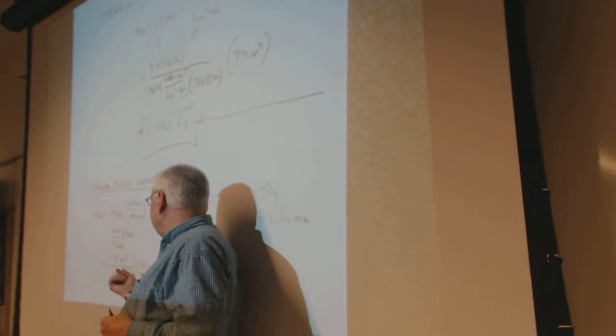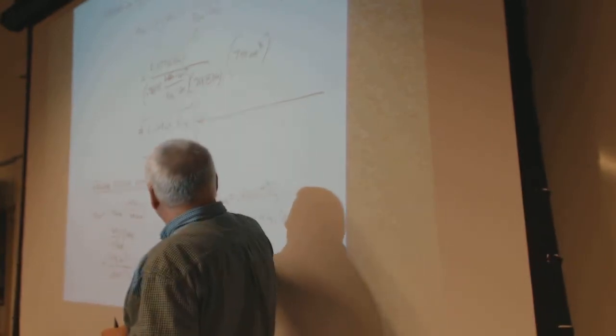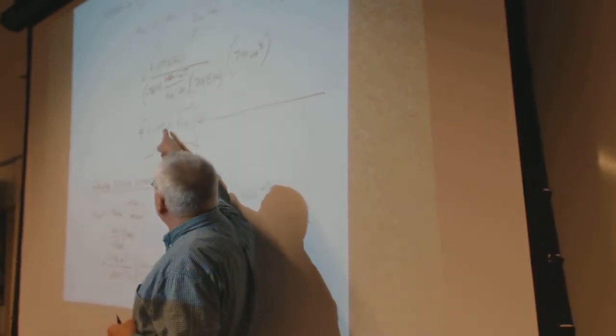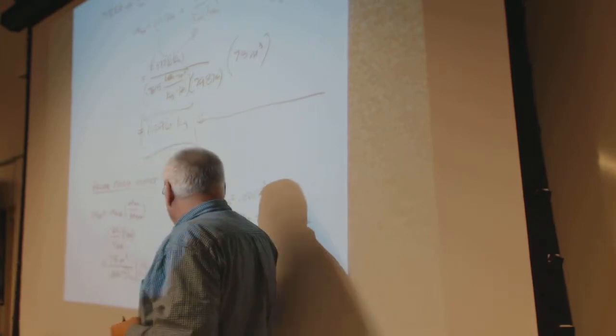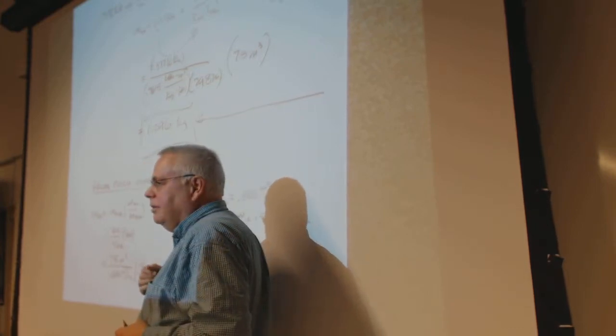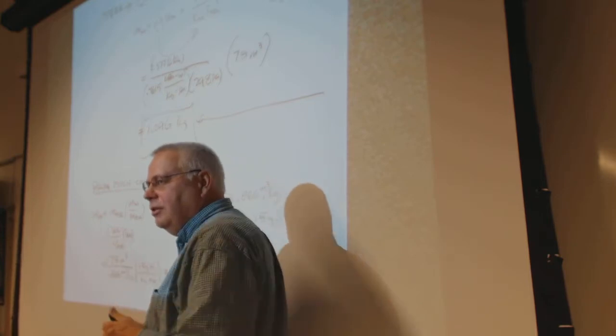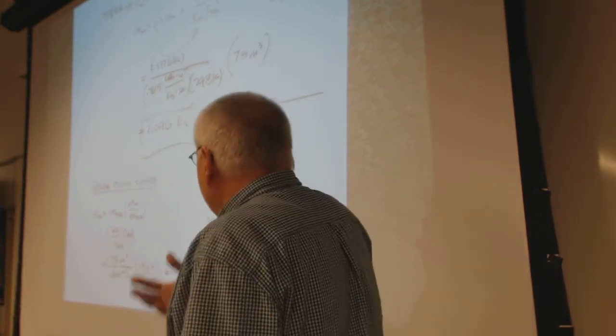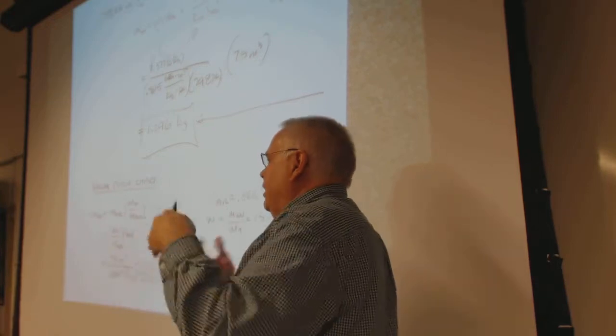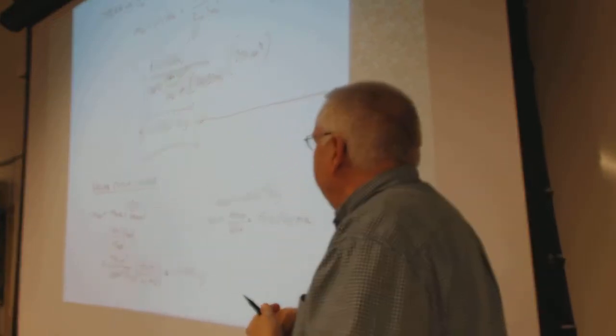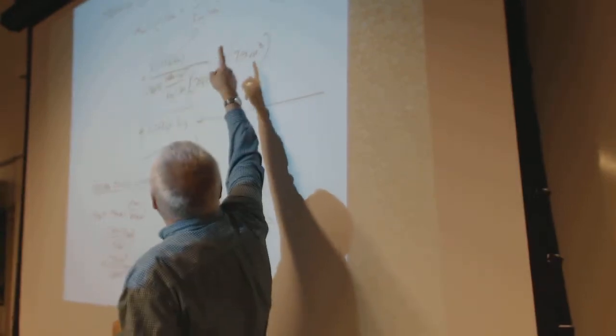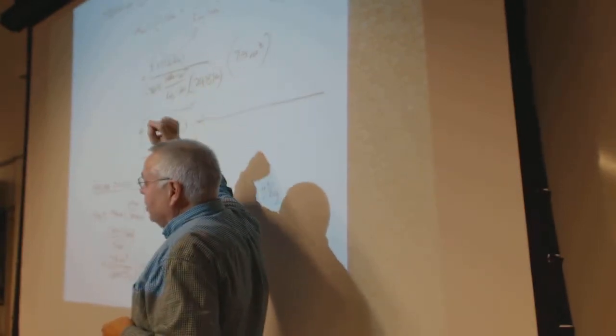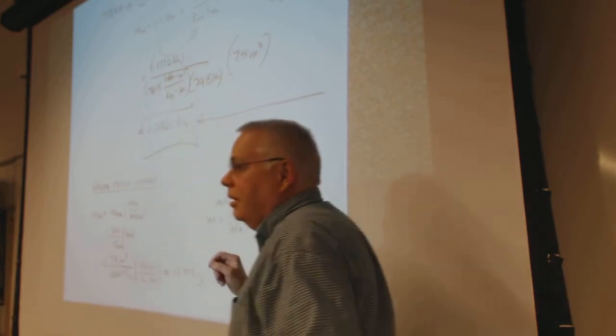Which is pushing our luck, because we really only have two sig figs in there, but that's compared to 1.296 kilograms, which is, I'm off by three grams, even though I was pretty much winging some of those numbers. So, there's multiple ways of getting to the same point, but the point being that psychrometric chart, you didn't have to deal with the R values and conversions and all that stuff. It's a pretty neat trick.